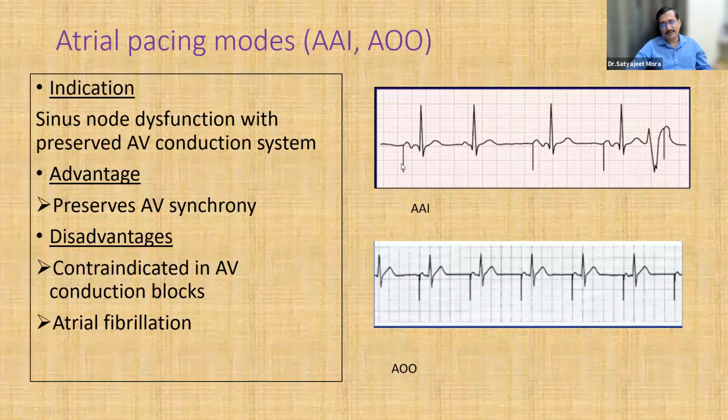So the pacemaker has time delays for the atria as well as for the ventricle. So it will wait till a predetermined time, which is fixed. And once it senses an impulse, it doesn't fire. If it doesn't sense an impulse, it fires. So this is a very important concept, that there is a time delay that the pacemaker has for detecting an impulse. So it will just wait around that time for a small fraction of a second, and if it detects the impulse, it will not fire.